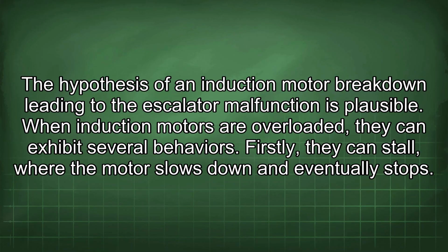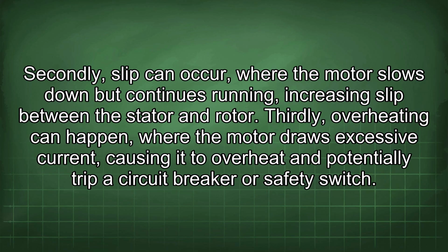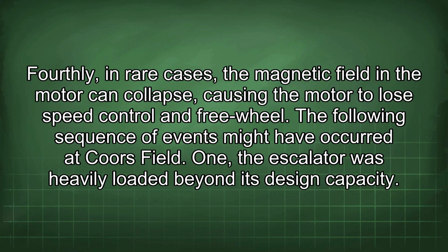The hypothesis of an induction motor breakdown leading to the escalator malfunction is plausible. When induction motors are overloaded, they can exhibit several behaviors. Firstly, they can stall, where the motor slows down and eventually stops. Secondly, slip can occur, where the motor slows down but continues running, increasing slip between the stator and rotor. Thirdly, overheating can happen, where the motor draws excessive current, causing it to overheat and potentially trip a circuit breaker or safety switch.